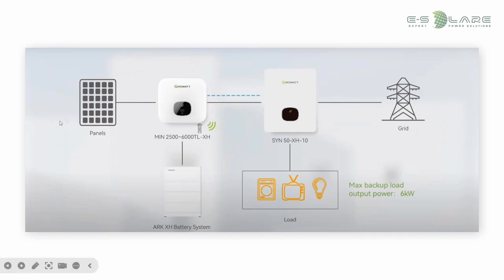This is the diagram for the whole system. We're connecting two panels and batteries to our MIN-XH inverter and connecting to SYN. And this one will supply the AC to the MIN-XH and will transfer power from MIN-XH to the backup load when the power is off, when the grid is off.